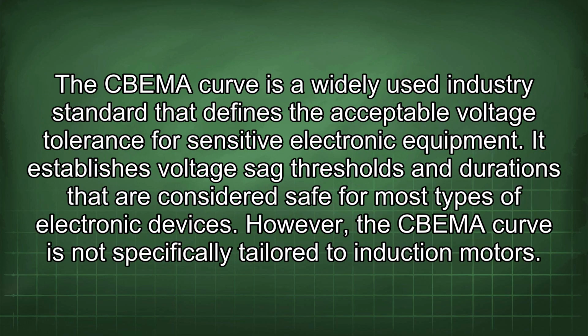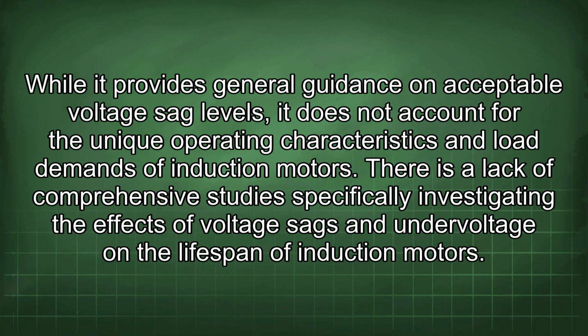The CBEMA curve is a widely used industry standard that defines the acceptable voltage tolerance for sensitive electronic equipment. It establishes voltage sag thresholds and durations that are considered safe for most types of electronic devices. However, the CBEMA curve is not specifically tailored to induction motors. While it provides general guidance on acceptable voltage sag levels, it does not account for the unique operating characteristics and load demands of induction motors.